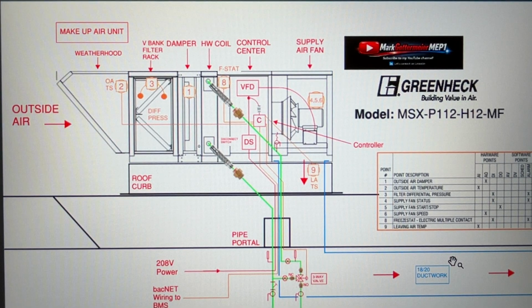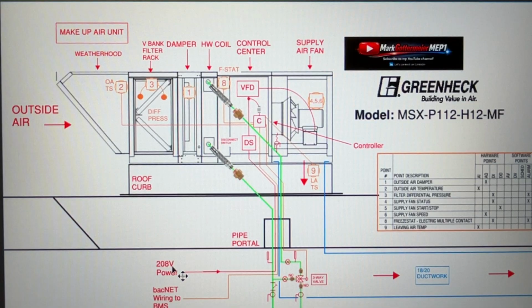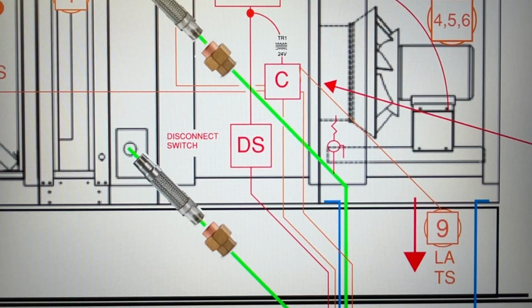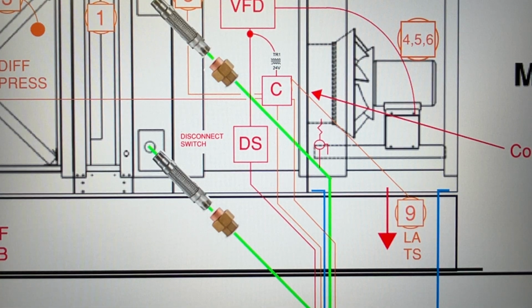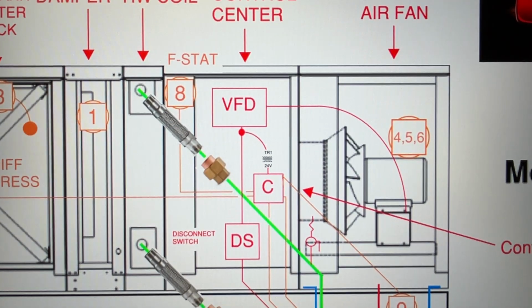Next, I'd like to talk about the controls, how the system's controlled. So I'm going to touch base here on the power first, and then we'll get into controls. From a panel in the building, we have our 208 power to be able to turn the unit on and off. That runs through a pipe portal on the roof, and it terminates at this disconnect switch. So this disconnect switch, let me zoom in on that. That disconnect switch right here will be your on and off. So this will be an access door up on the roof. So that'll be our on and off to the unit.